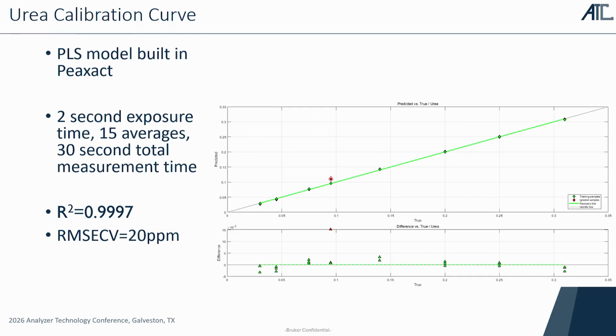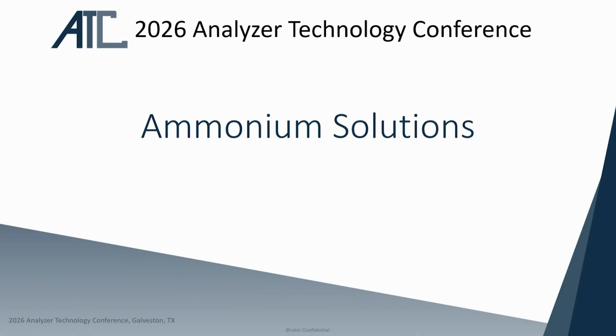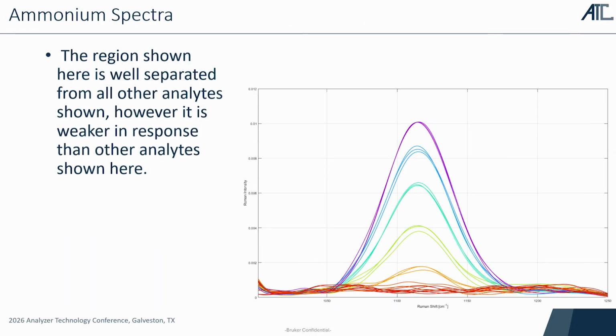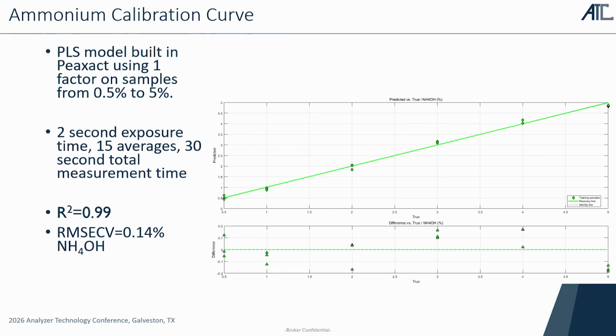The width of the peak does add some challenge to it, but we're able to overcome that with chemometrics. And 0.99, RMSE of 20 ppm. 2-second exposure times. Ammonium solutions, this is very common as well. Oil and gas, chemical, well separated from other analytes. So the specificity is there on all of these peaks. And where there is a little bit of convolution, we're able to overcome it, and very quickly. So again, R² 0.99. And error cross-validation of 0.14.